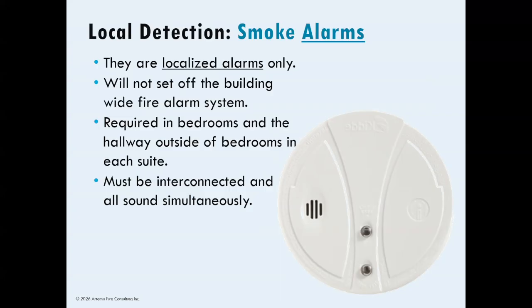These smoke detectors are not to be confused with smoke alarms, which are found inside of suites and only sound within that individual suite. Per the BC Building Code, they're required in each bedroom and in the hallway immediately outside of the bedrooms. They are also required to be interconnected so that if one goes off, they all sound. Smoke detectors, when activated, will set off the building-wide horns or bells. Smoke alarms will not.